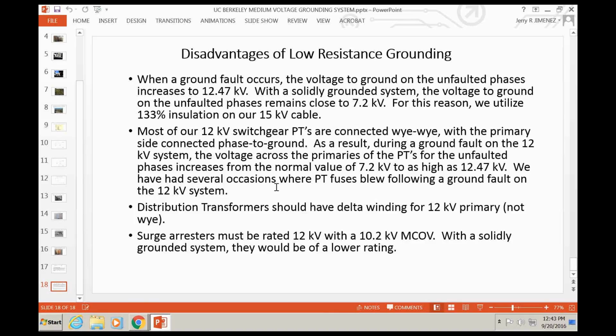Did you lose the PTs themselves? No, the fuses. Fuses are current limiting, fast acting. PTs were fine. Yeah, they're often such a high ratio. They're a very vulnerable part, at least in my history, our experience. Yes. Early in the burn-in phase of a new switchgear lineup, I put in maybe about 10 switchgear lineups during my time, and that was always the first place if we were going to get a failure. Unfortunately, it happened with some consistency.